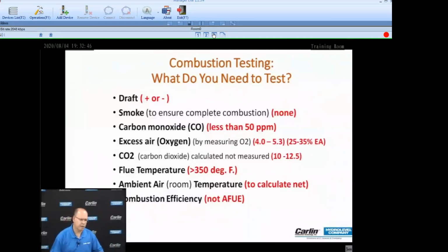Ambient air, why do we use ambient air temperature? Why do we need ambient air temperature? Well, the ambient air temperature is added with the combustion air. So at the end of the process, you would have to subtract your ambient air temperature to fully understand what your flue temperature is, to know what your combustion temperature was in the combustion process.